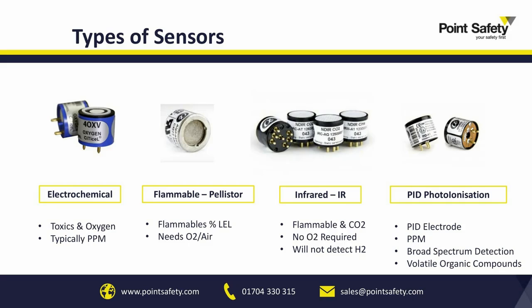But when selecting these, you need to bear in mind that they will not pick up hydrogen. So if hydrogen is a requirement, you will need a Pellistor, or at low levels an electrochemical, detecting hydrogen at ppm levels.